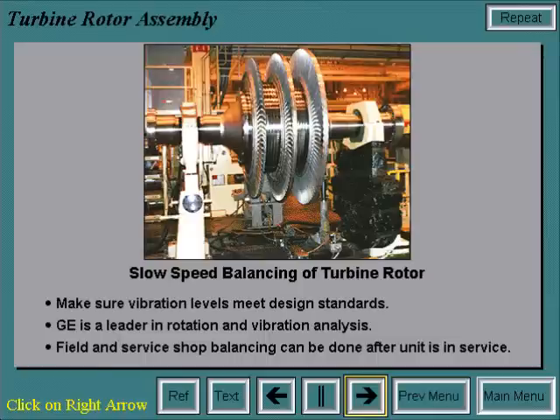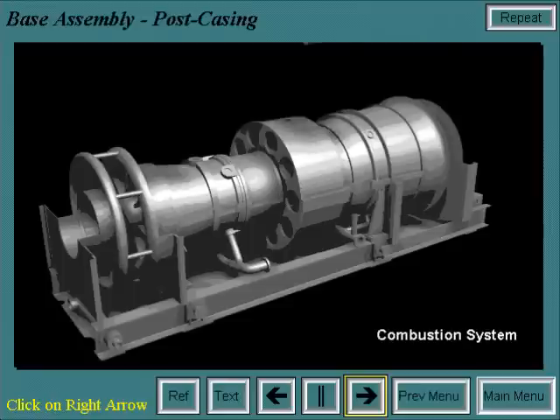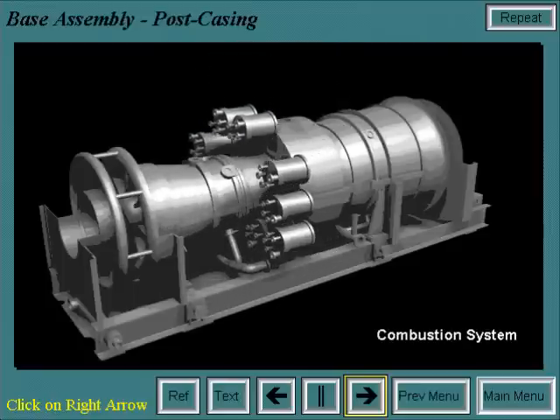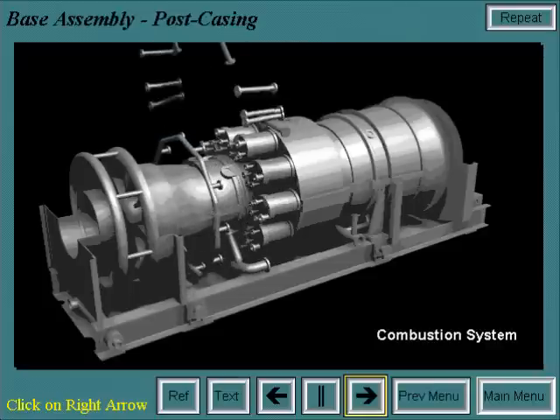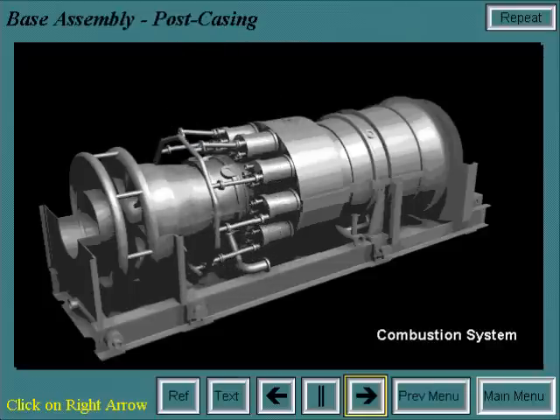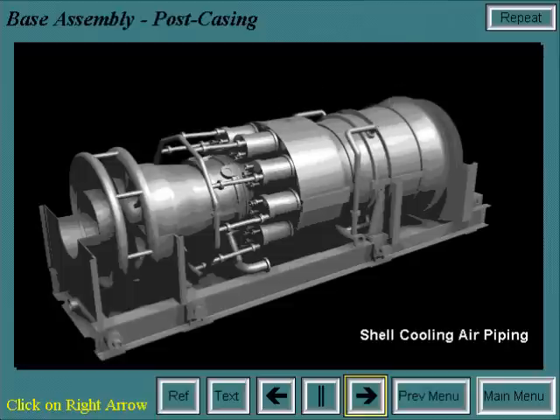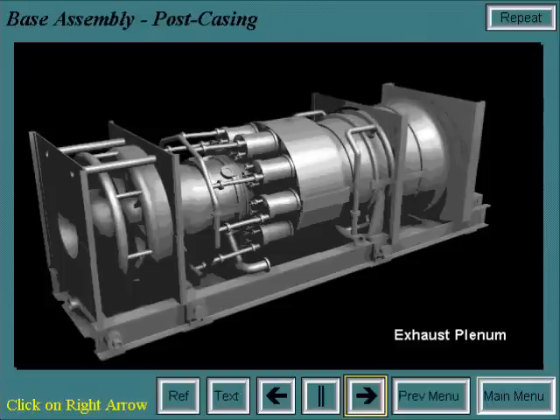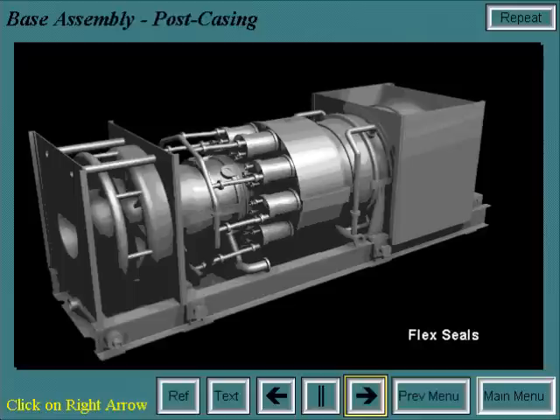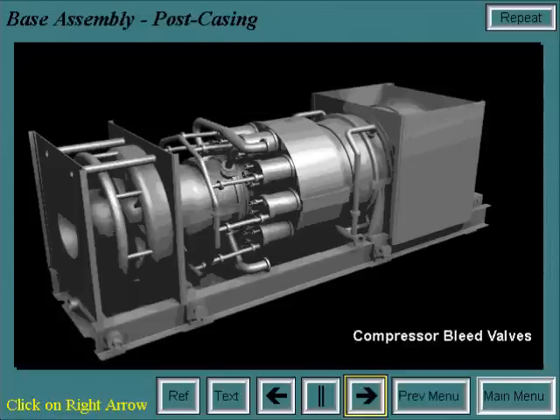Once the casings are on, the combustion system is installed. Next, the shell cooling air piping is installed. Air comes from off-base blowers to facilitate shell cooling in the turbine and exhaust casings. Then the inlet plenum is installed, and after this, the exhaust plenum is put in place. The flex seals keep the exhaust gases from escaping into the turbine compartment or out to atmosphere while allowing for thermal expansion. Finally, the compressor bleed valves are installed.